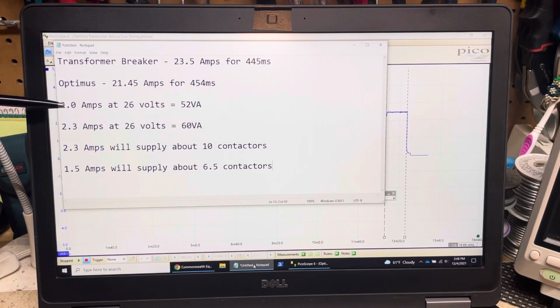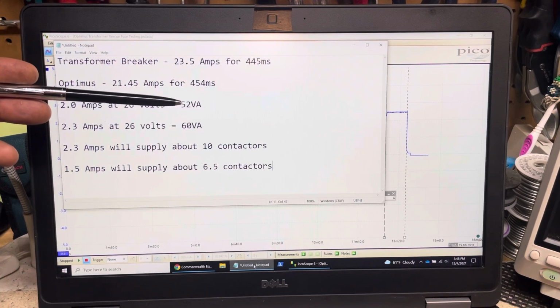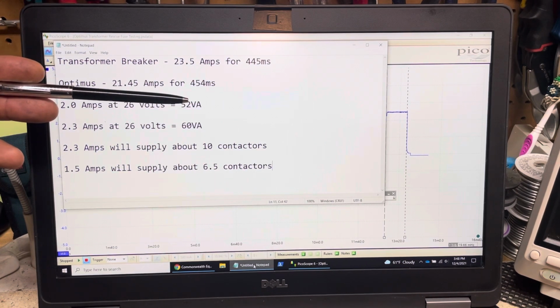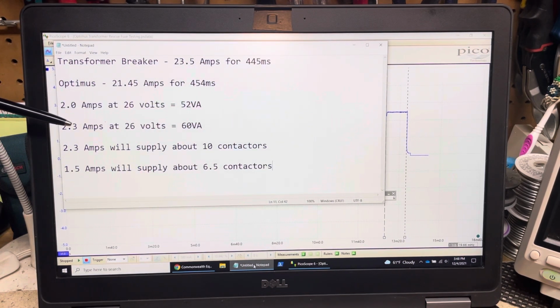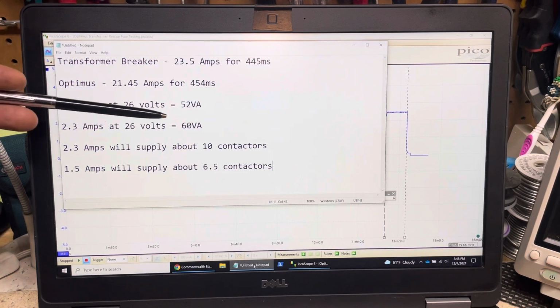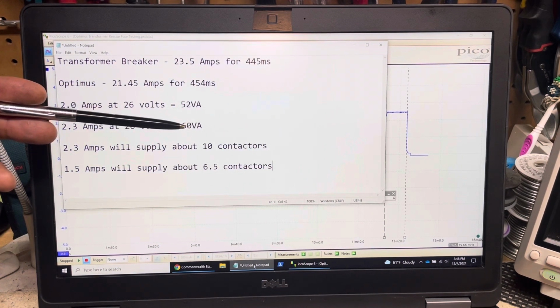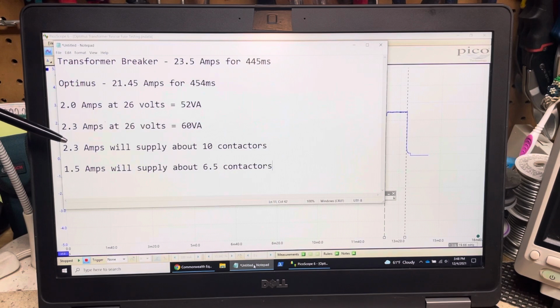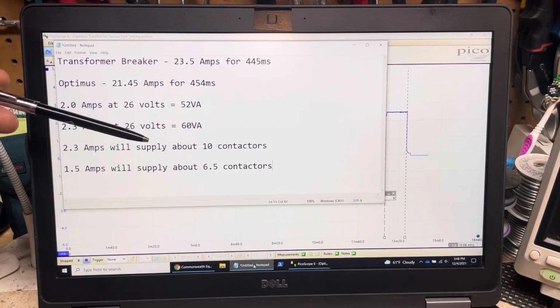So if I supply a circuit with 2 amps at 26 volts, which is what Optimus was doing, that's about a 52 VA circuit. If we're able to supply 2.3 amps, we're at about 60 VA. To give you some perspective, 2.3 amps can supply about 10 contactors, providing they don't all turn on at the exact same time.